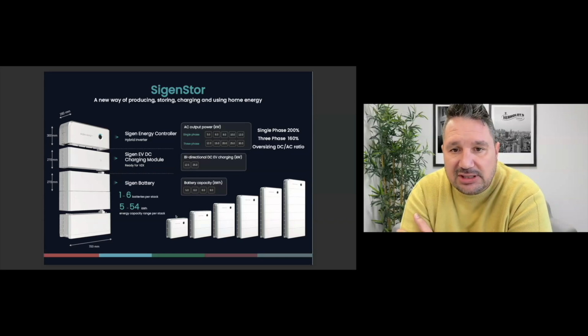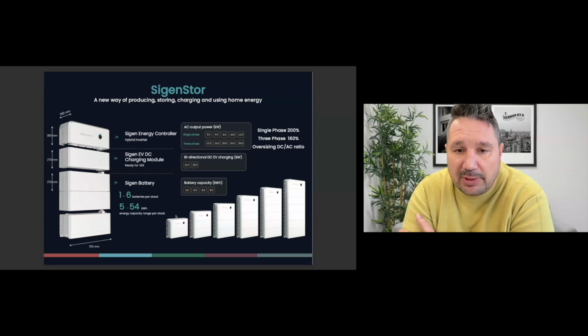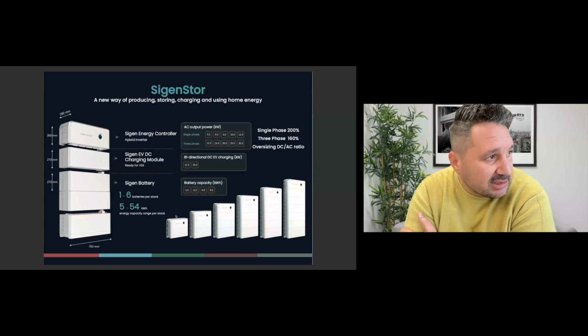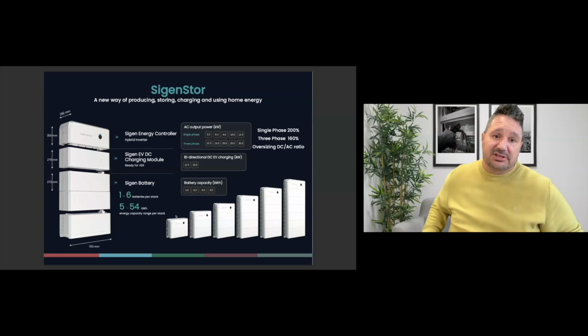These inverters range in single phase from 5 kilowatts all the way up to 12 kilowatts, and in three phase from 12 kilowatts all the way up to 30 kilowatts. We recently helped an EPC complete a project building a 2.4 megawatt, 4.8 megawatt hour system with a 0 millisecond changeover from grid to off grid at a cable factory in South Africa, using these stackable solutions and making use of the 25 kilowatt inverter systems.